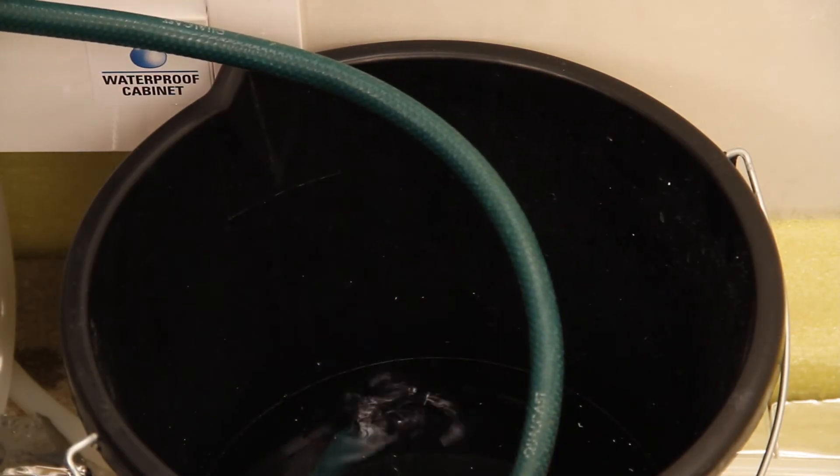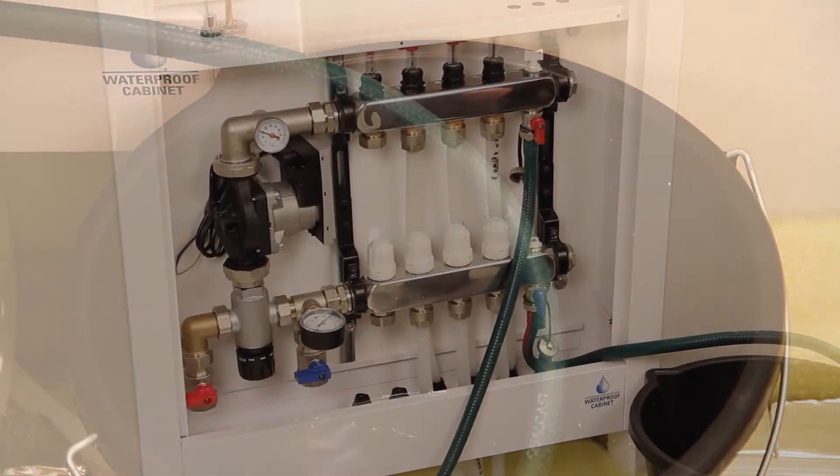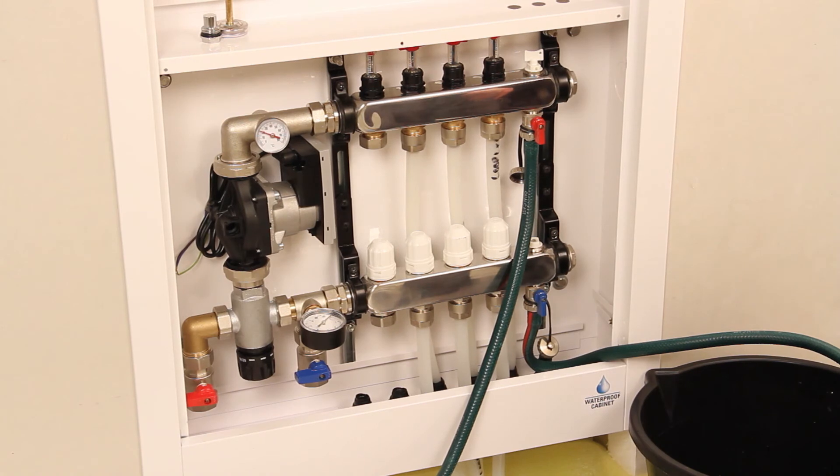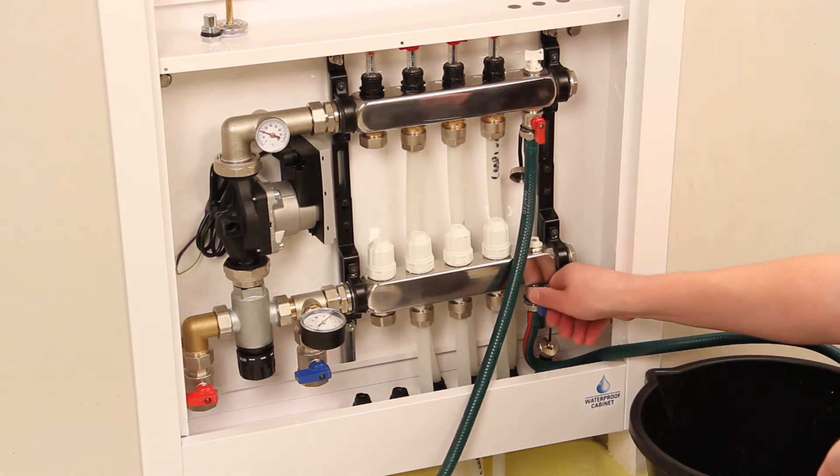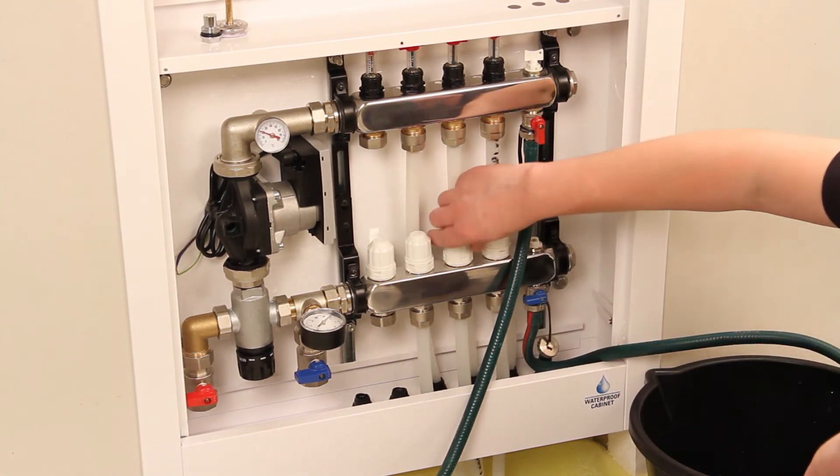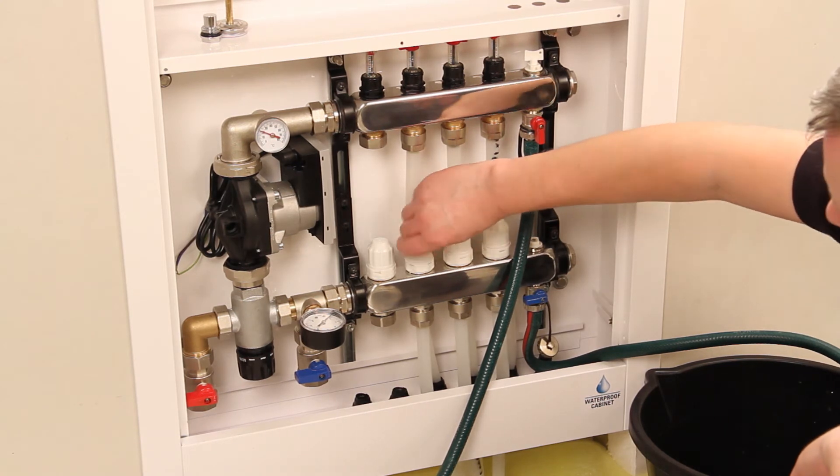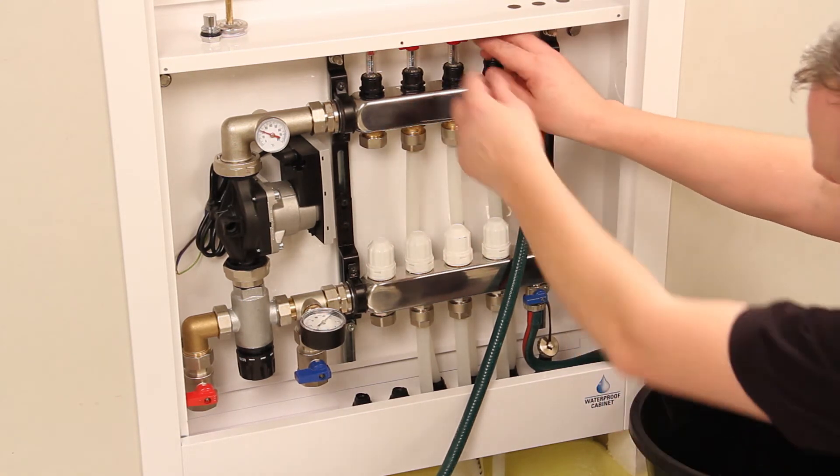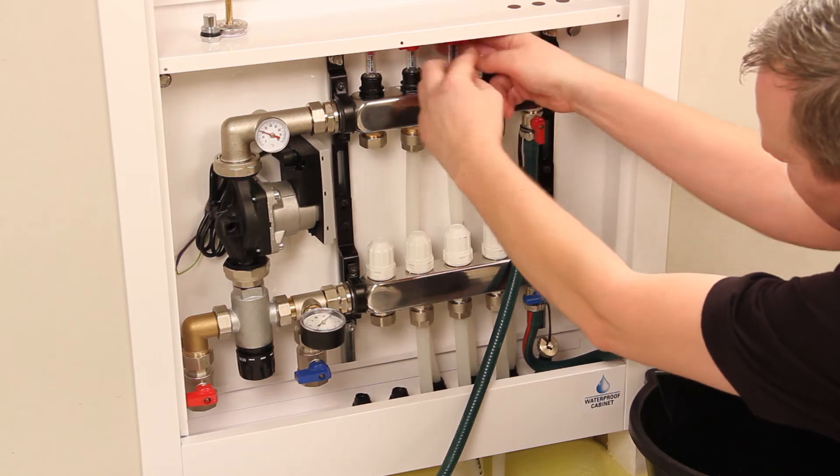Once the last circuit of pipe has been purged and filled, leave the flow gauge and return valve open. Close the drain off tap on the lower return bar. Reopen all the other flow gauges and return valves on all circuits that have pipe connected.